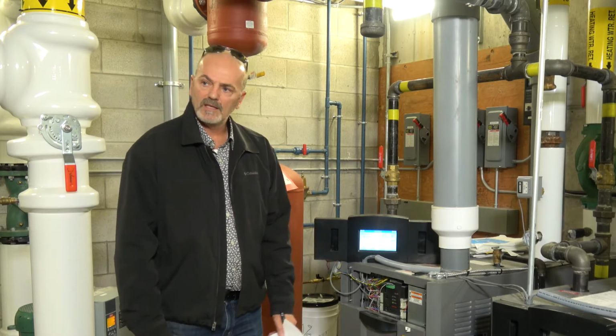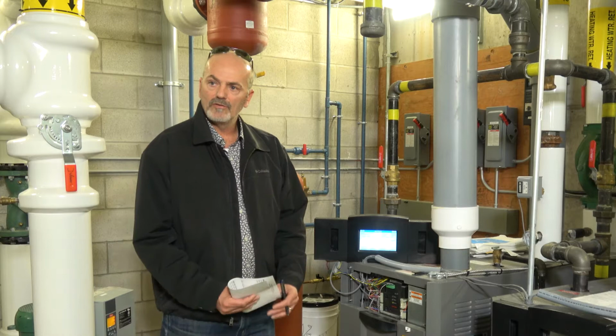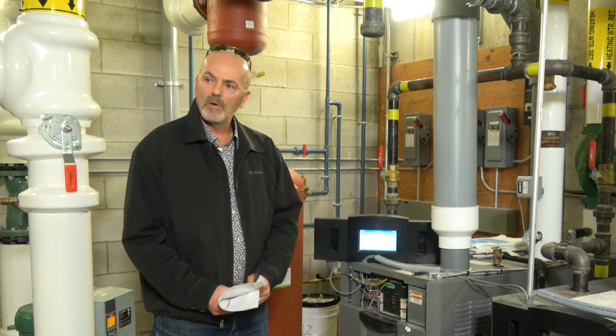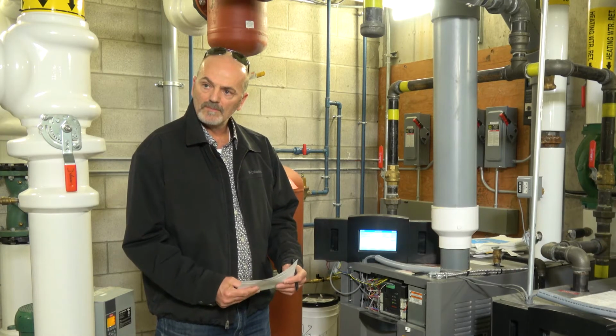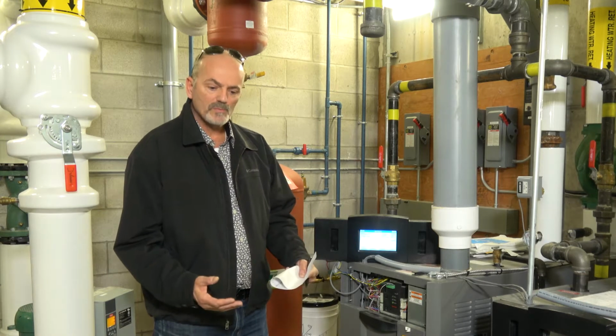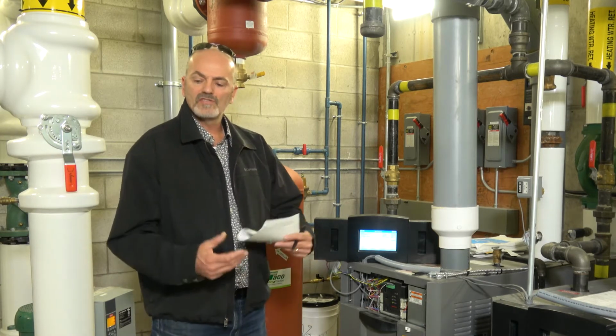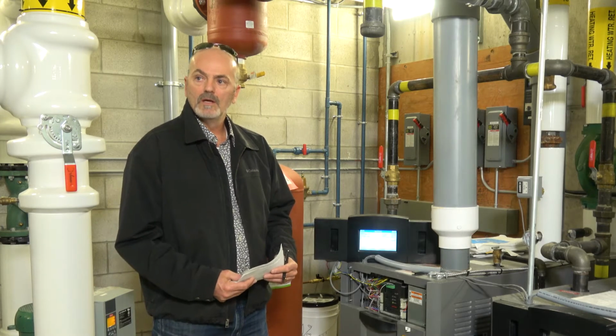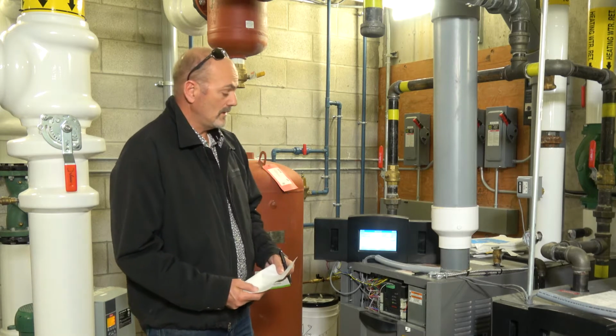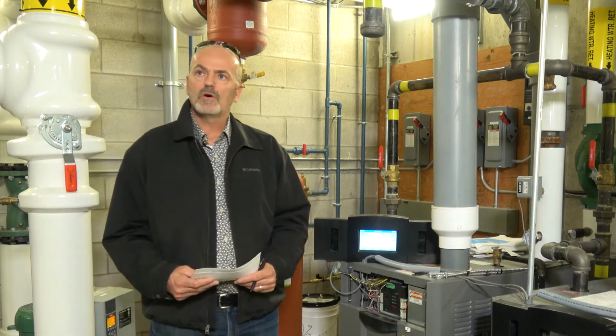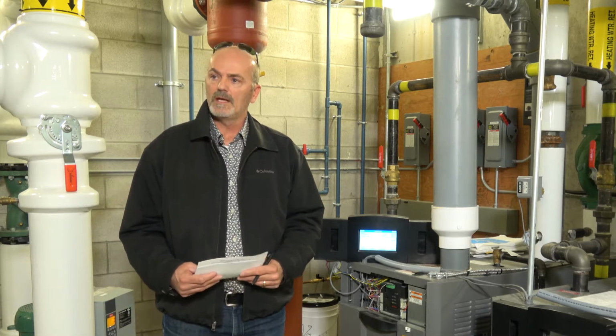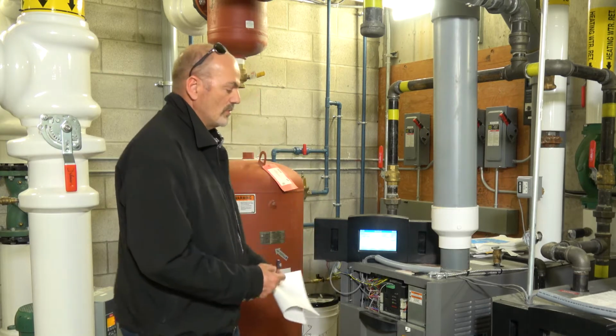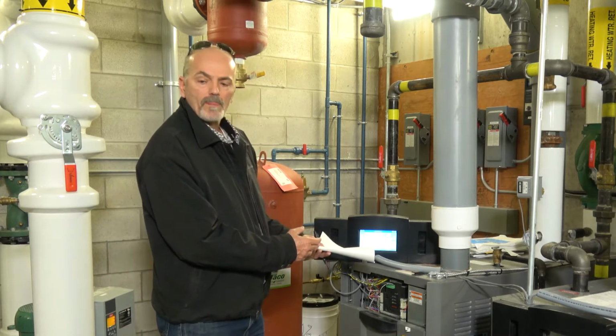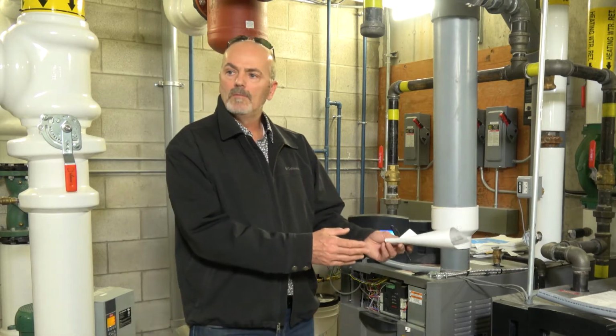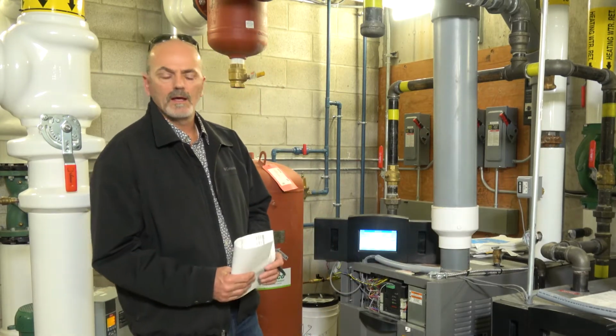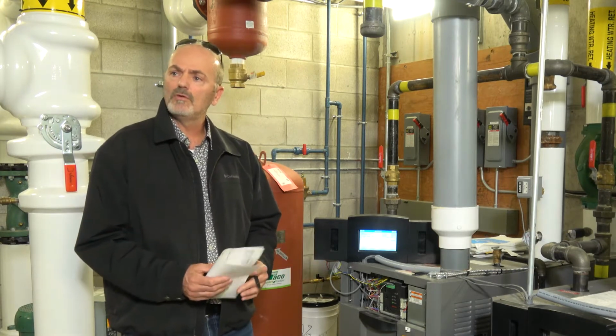If one boiler can't keep up, and/or if that boiler fails and locks out, the secondary boiler will come online in its place, as a replacement to the one boiler that's offline, or a supplemental input for quicker recovery for the other main boiler that's also running. Okay? They have what's called lead lag function, so they get equal wear time. So every so many hours, this boiler will become backup, this boiler will become first stage, and they will run, I think it's factory programmed every 72 hours.